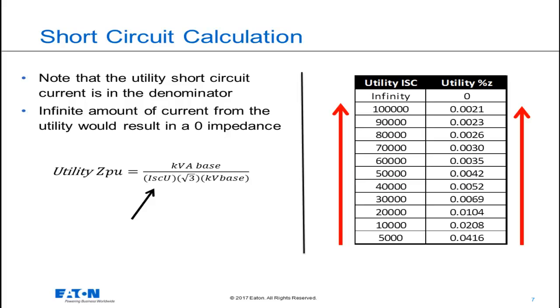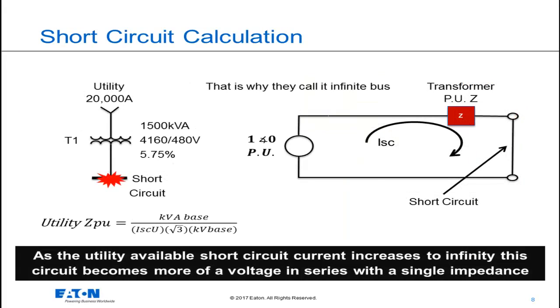This is significant because it tells us that as the utility available short circuit current gets larger, approaching infinity, the equivalent utility impedance gets smaller and approaches 0. Infinite amount of current from the utility results in 0 impedance of the utility. Look at this circuit again.